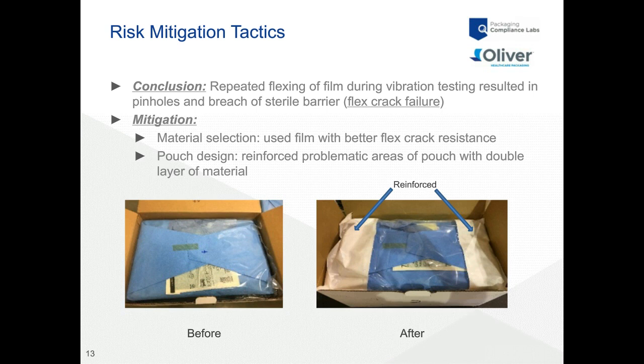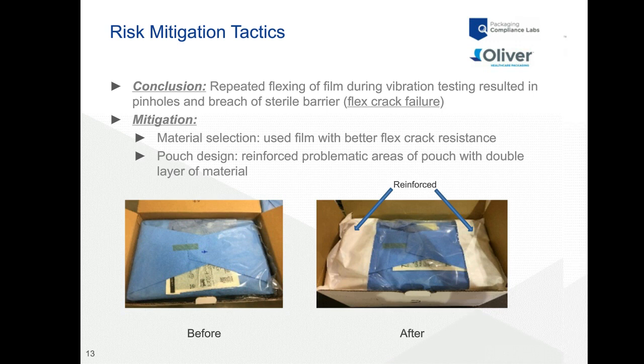Mitigation tactics included a two-pronged approach. Material selection was critical. The message here is that different materials will have different flex crack resistant properties, so it's very critical when you have a flex crack failure to understand the materials at play and how good they are at resisting flex crack. In this case, we also looked at redesigning the pouch.